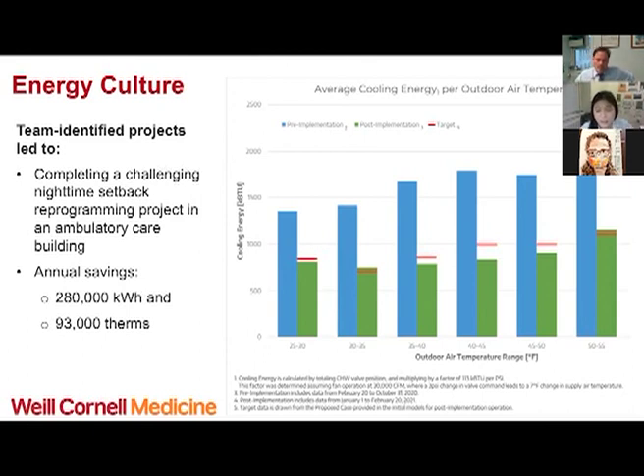So just over time, our central plant got used to running them constantly, 5 or 6 out of the 7 running, 24/7, 365. Well, thanks to Ron kind of bringing it up, we worked with a talented engineering firm to implement completely new BMS code on the air handling units and the terminal units that allowed for proper, automatic staging without manual intervention. And now we're running at, I think, last I heard, 2 air handlers a night, and we're trying to drop it down further. So that's just incredible.